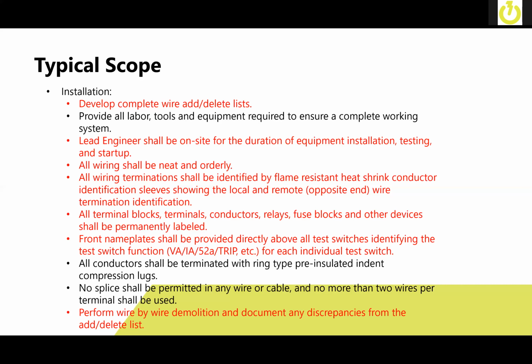Conductors terminated with ring type pre-insulated indent compression lugs. What happens a lot of times is if you use fork terminals and you try to put more than one lug on that terminal and you have forks, those can become very easily loosened and they can fall out. Using the ring type ensures that you make a solid connection and it gets tightened down properly.